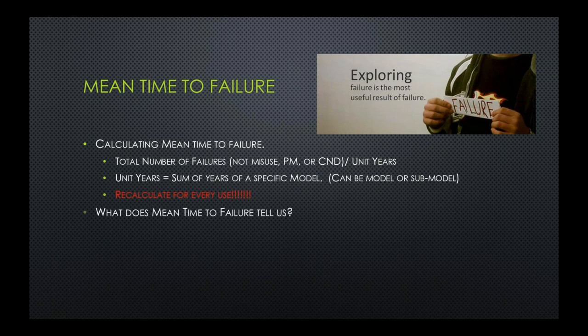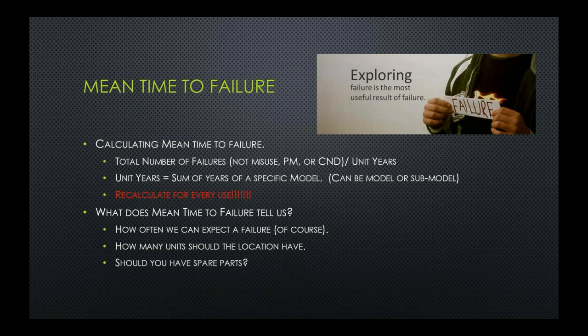But now, what does mean time to failure really tell us? Obviously, how often do we expect a failure. But it can also tell us how many units a specific location or hospital system should have, depending on the area it covers. And it can also answer: should we have some spare parts on hand? So what we're going to do is use mean time to failure to calculate the right sizing of equipment.